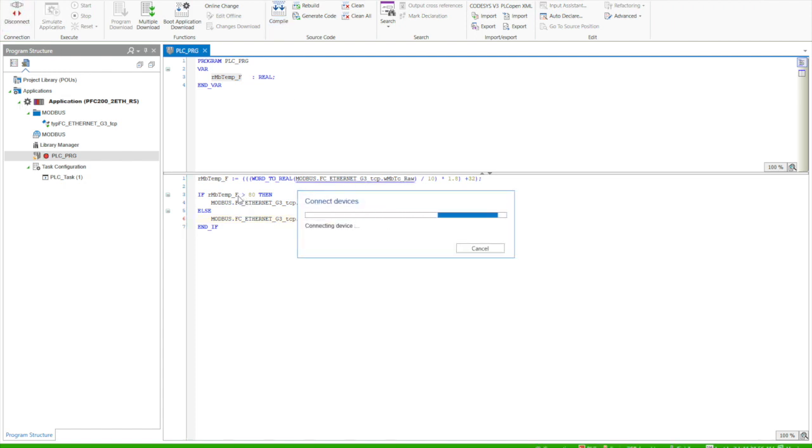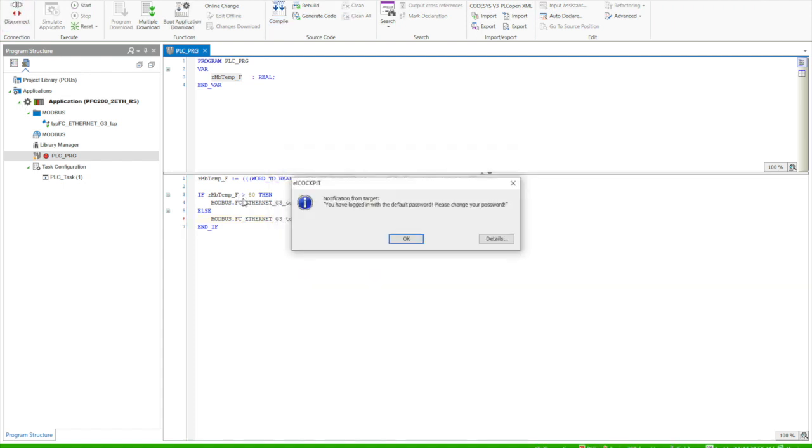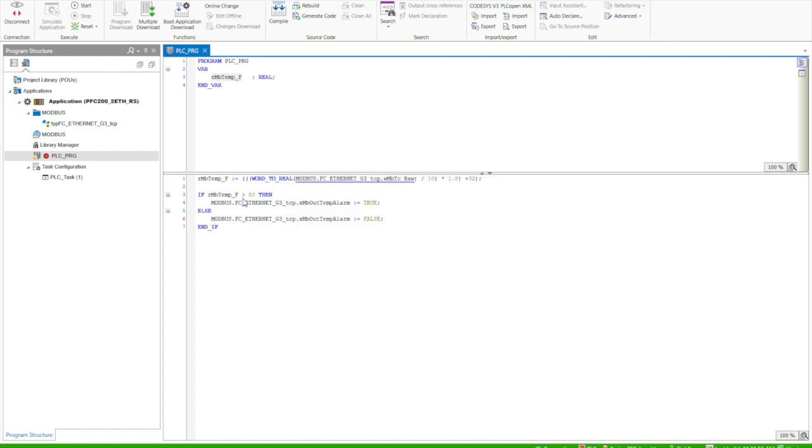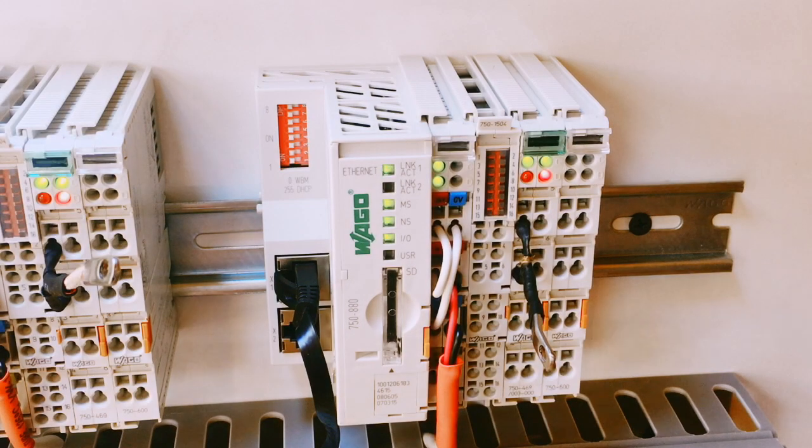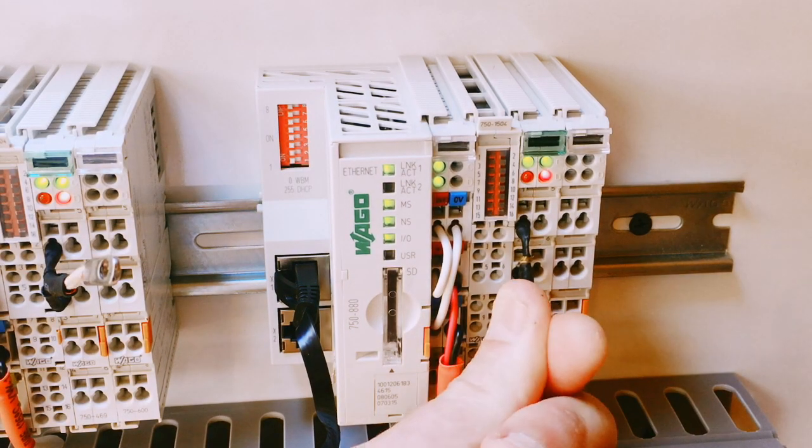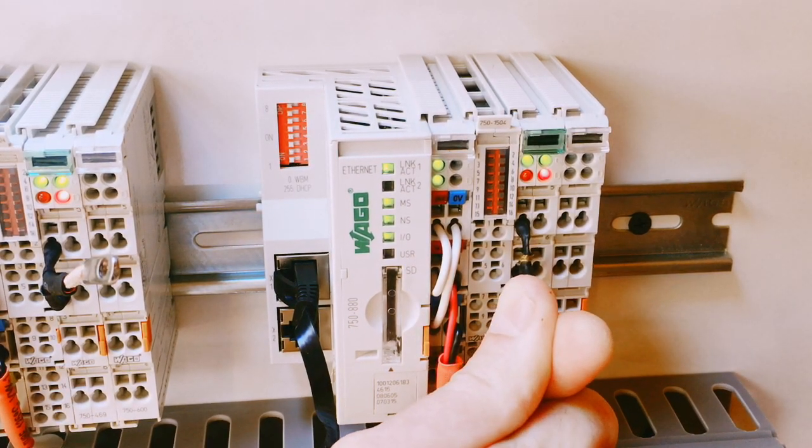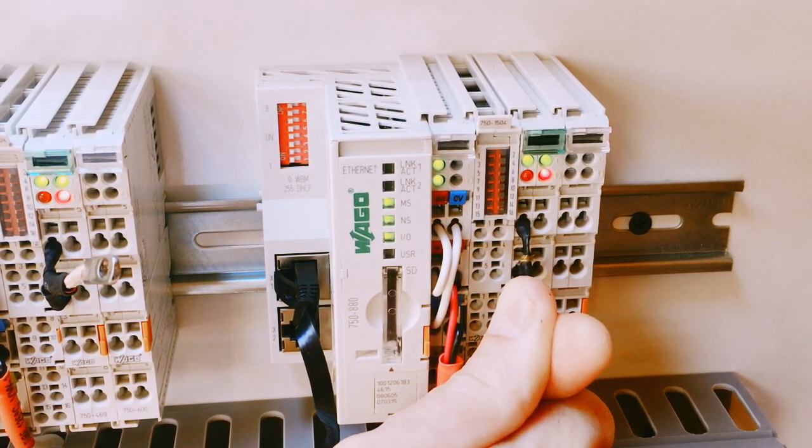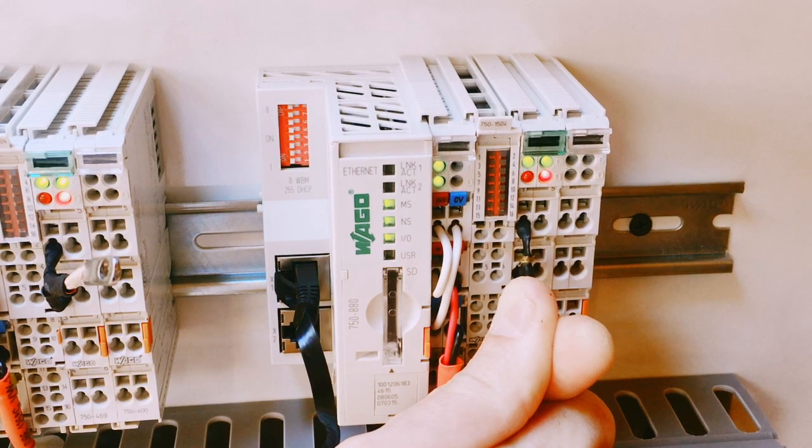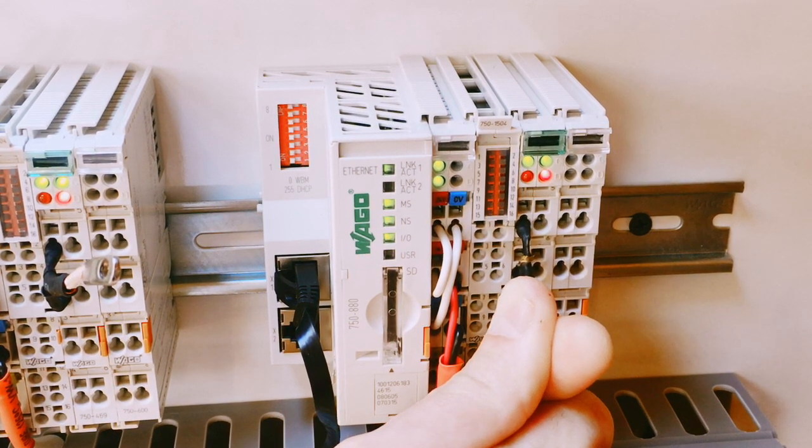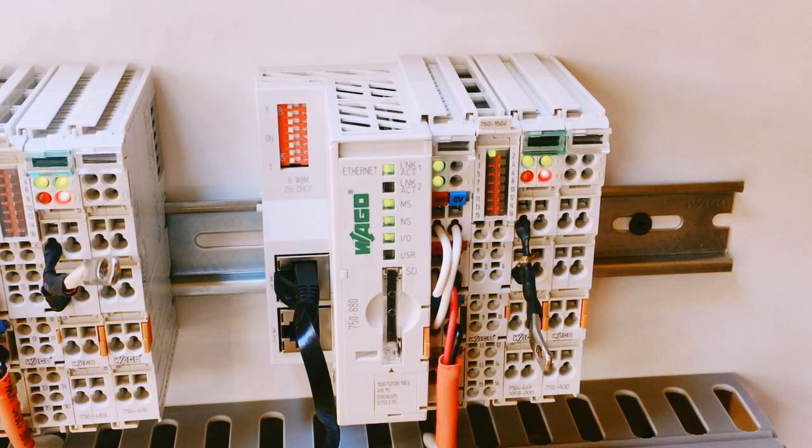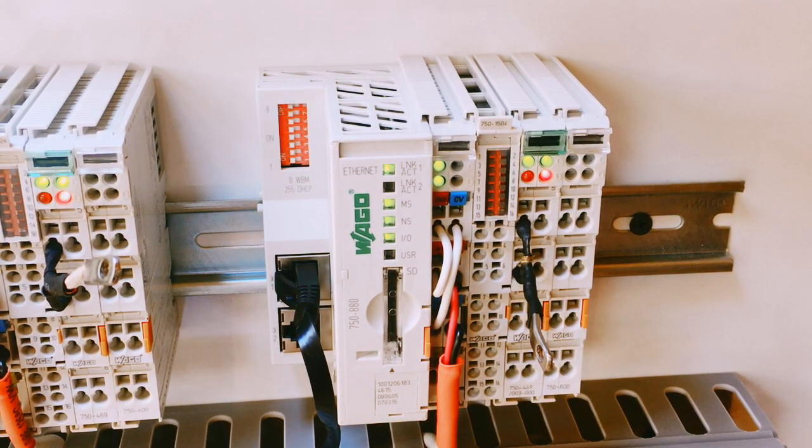We'll compile it, and then we'll connect to the controller and download the code. Now once we've downloaded, we'll put this into run, and we'll have good communications. You can see our value, and if I just hold this thermocouple, you'll see my output will go true once I hit 80 degrees. If I let go, it should also reset itself back to false.